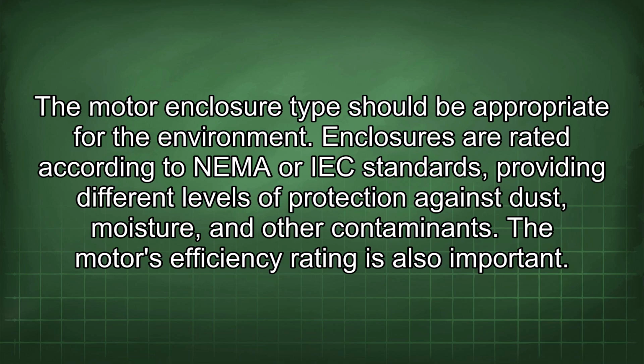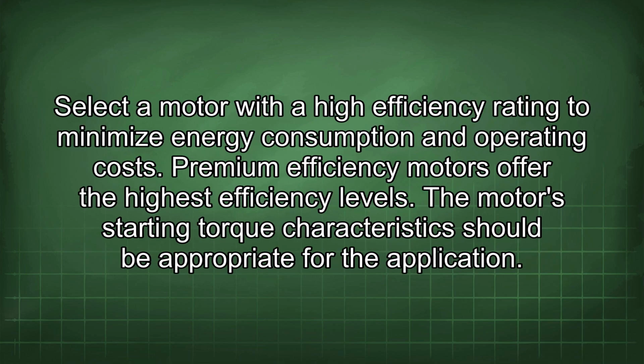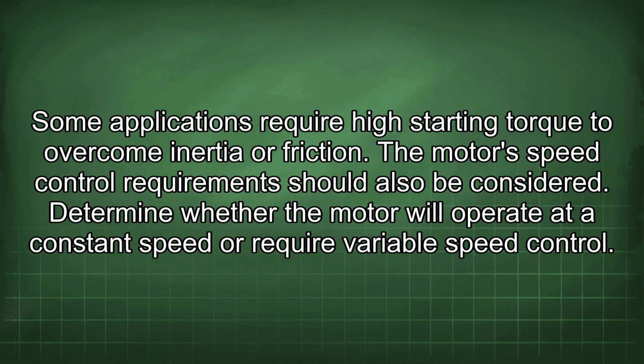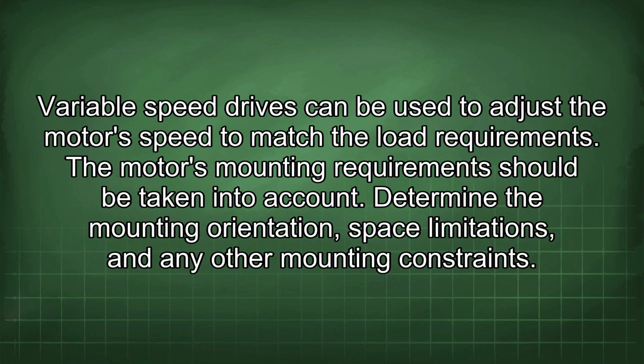The motor's efficiency rating is also important. Select a motor with a high efficiency rating to minimize energy consumption and operating costs. Premium efficiency motors offer the highest efficiency levels. The motor's starting torque characteristics should be appropriate for the application. Some applications require high starting torque to overcome inertia or friction. The motor's speed control requirements should also be considered. Determine whether the motor will operate at a constant speed or require variable speed control. Variable speed drives can be used to adjust the motor's speed to match the load requirements.